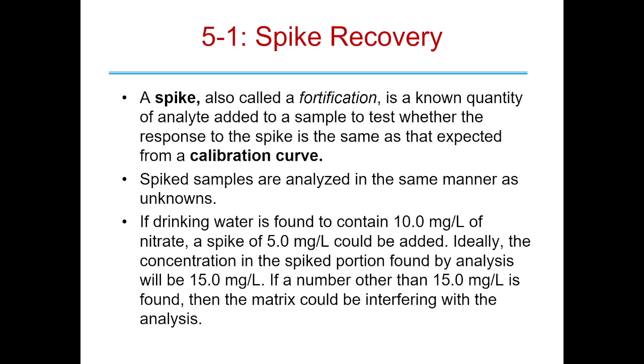All right, spike recovery. Spike, also called a fortification. This is a known quantity of analyte added to a sample to test whether the response to the spike is the same as that expected from a calibration curve. Spike samples are going to be analyzed in the same manner as the unknowns.